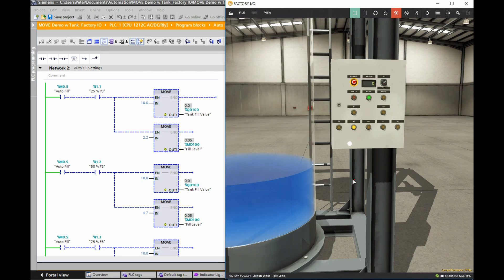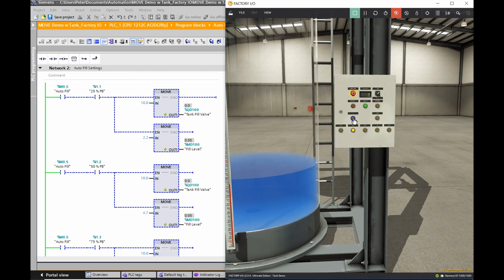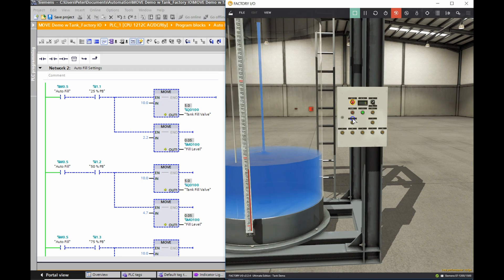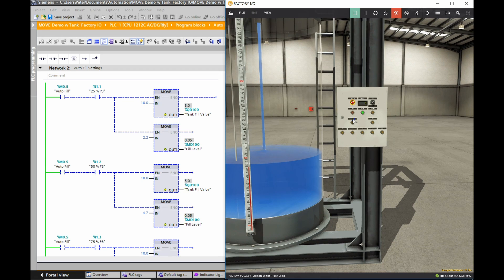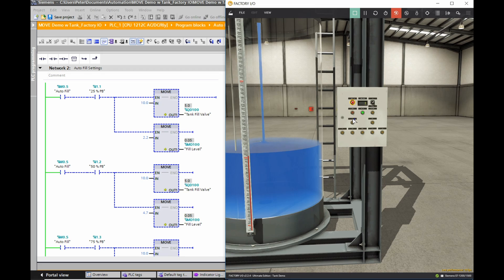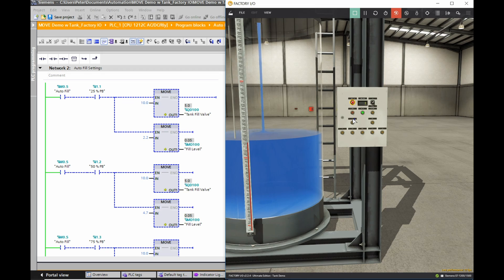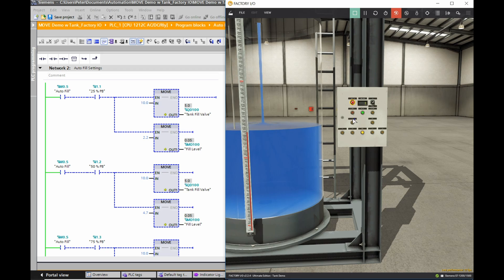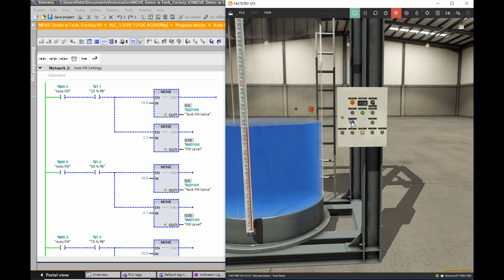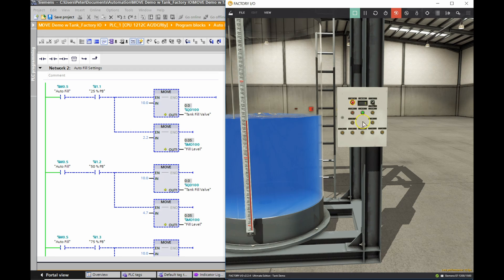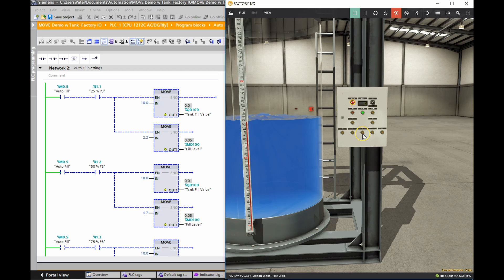If I now keep going and fill the tank and I get to 50 percent, my next light should turn on. So 50 percent is 300 to the top there, so 150 will be 50 percent. You can see that I may have to work a little bit on those values there because it came in a little bit too early. So I got 150 for my 50 percent range there. Once that water settles down, hopefully this light will turn on. Beautiful.